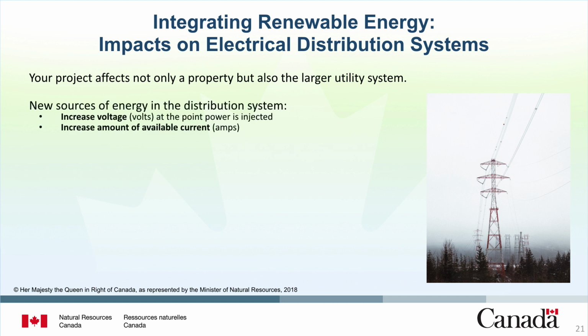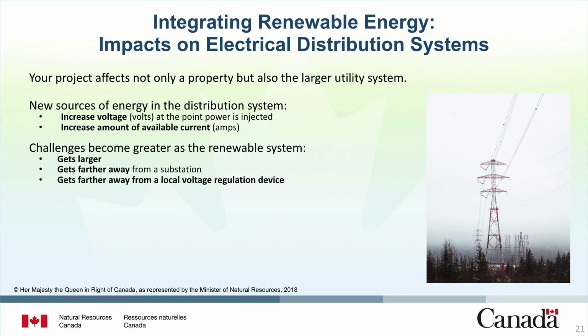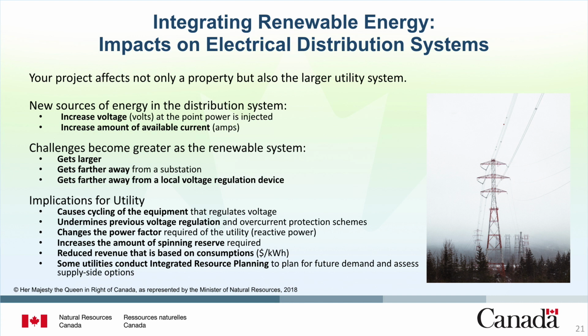For instance, new sources of energy in the distribution system both increase voltage at the point power is injected and increase the amount of available current. Interconnection challenges become greater as a renewable system becomes larger and is located farther from a substation and a local voltage regulation device. These circumstances have direct implications for the utility. Problems include cycling of the equipment that regulates voltage and problems for voltage regulation and overcurrent protection schemes.